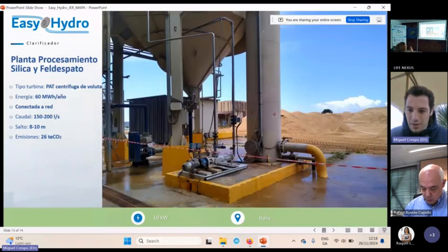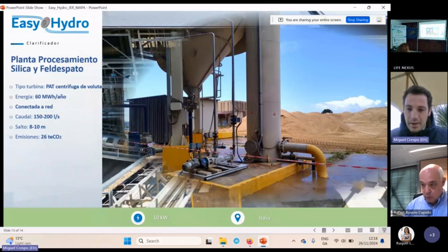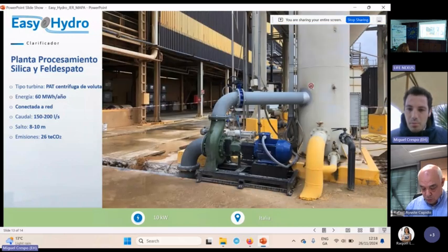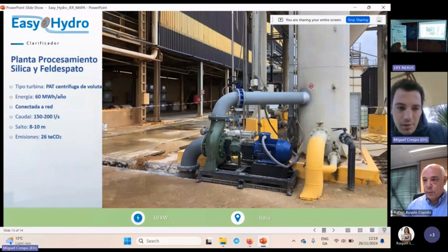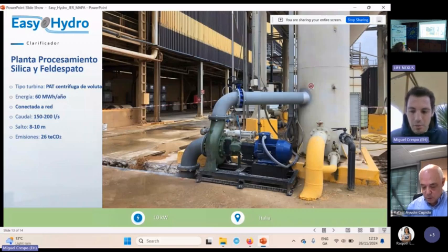So here is the before. The water was being discharged into a water pond. And here we have the after. We took this small pipe to turbine the flow, and with the electricity that was being produced, around 10 kilowatt, we directly feed some recirculation pumps nearby. With this installation running 24/7, we are generating about 60 megawatt hours a year and avoiding almost 30 tons of CO2 equivalents.